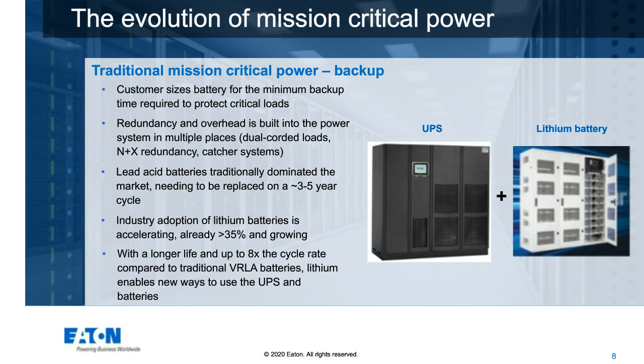So the industry adoption of lithium batteries, as we said, is accelerating already at an amazing rate. All of us in the industry are quite surprised by the interest level and the actual amount of lithium that we're shipping with our large UPSs. They provide a longer life, up to 8 times the charge-discharge cycle rate compared to traditional batteries, and enable us with new ways to use the UPS and batteries.